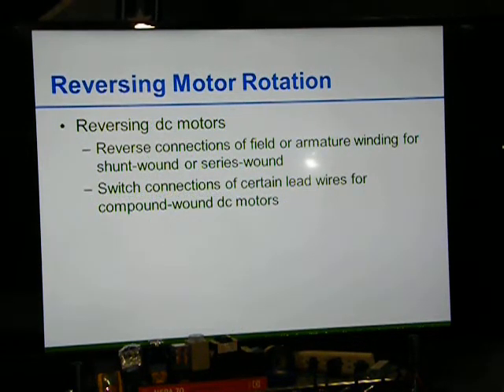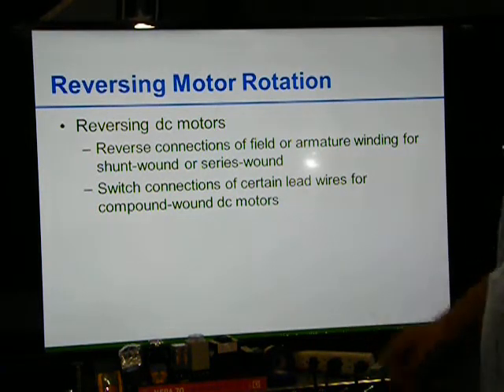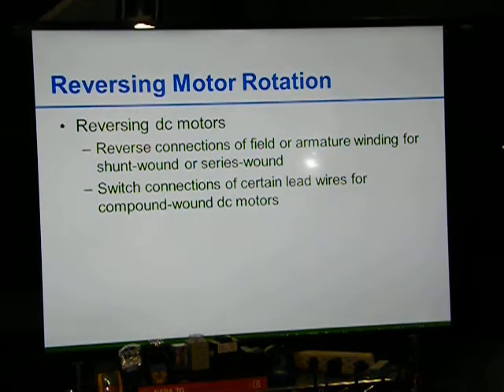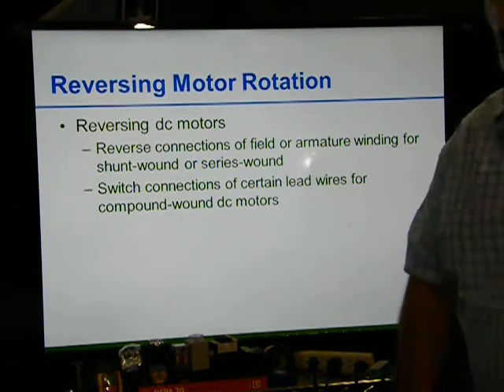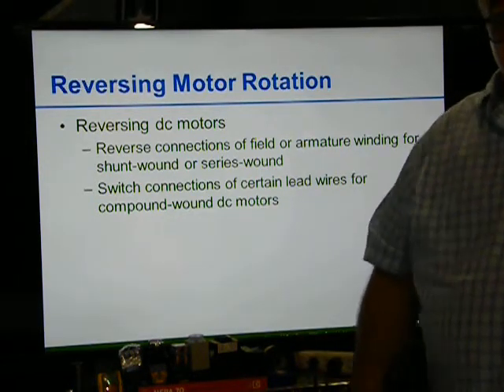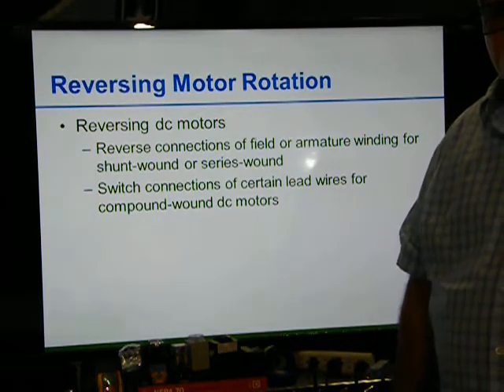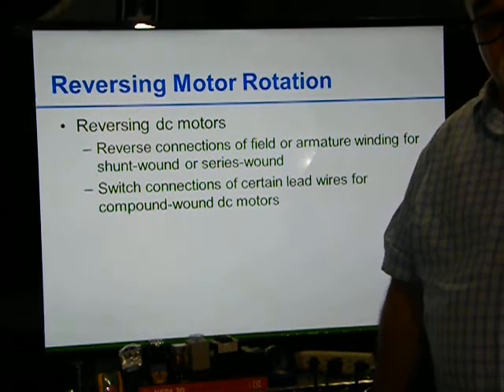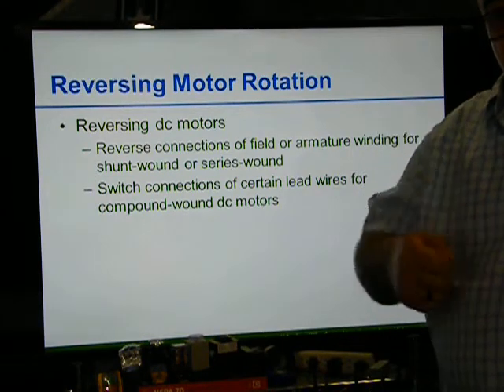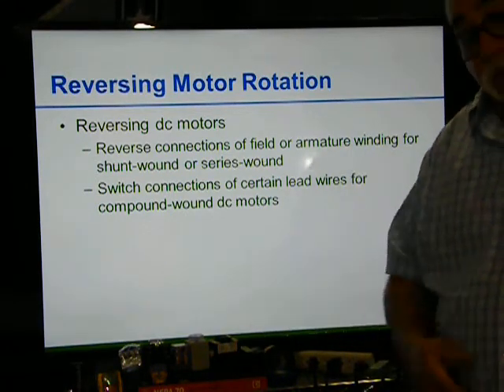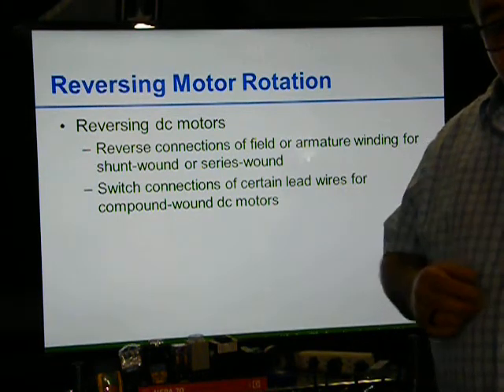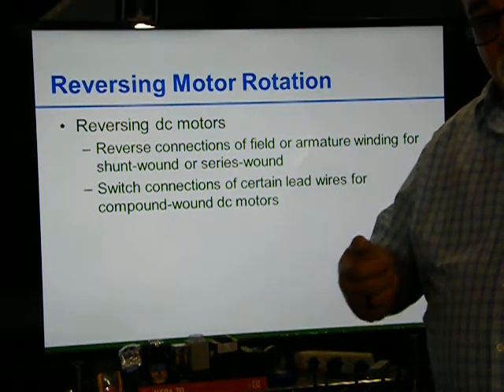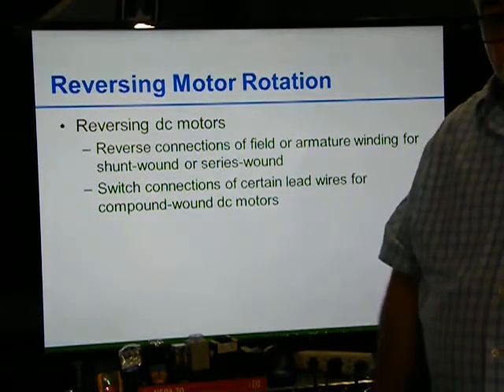Reversing DC motors: reverse the connections of the field or armature winding for a shunt wound and a series wound motor. The armature is up at the front. And then switch connections for certain lead wires for compound wound DC motors. It's just like a battery. If you have a tester at home, put it on DC and put your black lead on the positive and your red lead on the negative. It's going to give you a minus, whatever that voltage is. But if you turn around and put the red on the positive and the black on the negative, it'll give you a positive voltage. So all you're doing is changing the rotation.